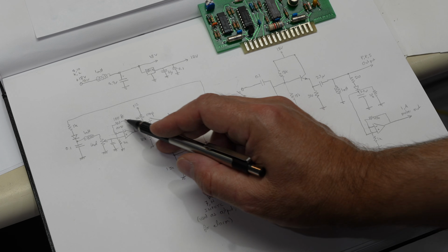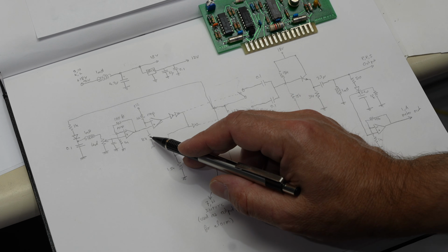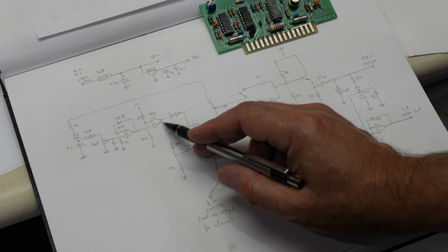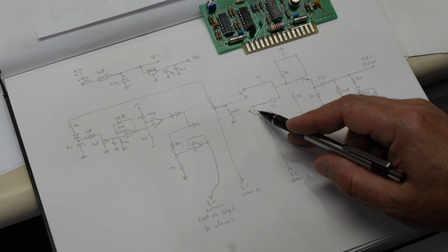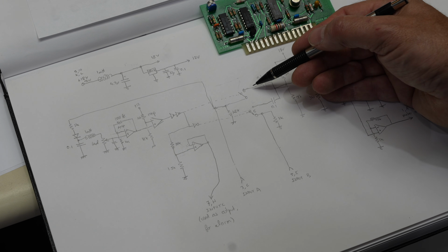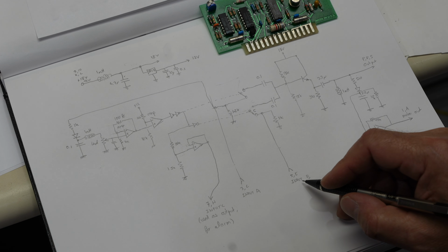And so there's a little amplifier, and then it goes into a comparator. And if it falls below the level, then switch A is open and the other switch is closed. So you switch over from A, which is normally the one that's on, to B. So input A is the normal and input B is the failover.